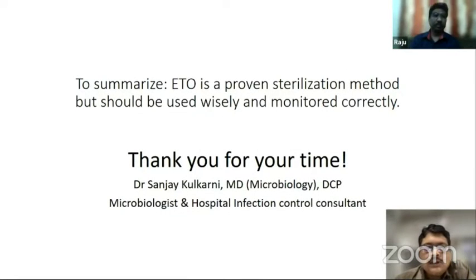To summarize, ETO is a proven and very effective sterilization method but should be used wisely and monitored correctly. A commonly asked question is whether phaco handpieces can be sterilized in an ETO sterilizer. First confirm with the vendor whether they are compatible with ETO sterilization. Since they are lumened instruments, it can be done, but a PCD should be used along with the phaco handpieces to confirm that penetration has happened properly.